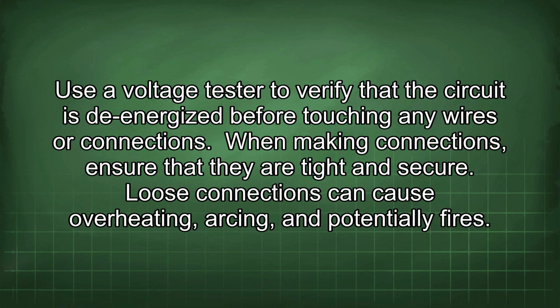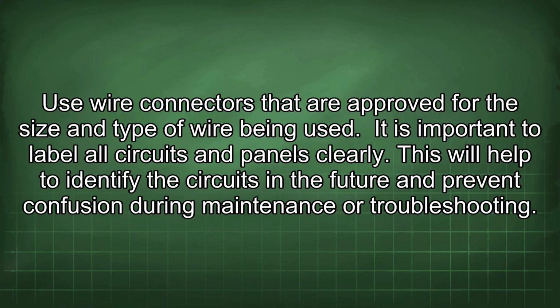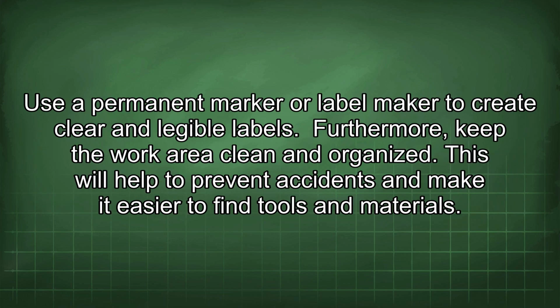When making connections, ensure that they are tight and secure. Loose connections can cause overheating, arcing, and potentially fires. Use wire connectors that are approved for the size and type of wire being used. It is important to label all circuits and panels clearly. This will help to identify the circuits in the future and prevent confusion during maintenance or troubleshooting. Use a permanent marker or label maker to create clear and legible labels.